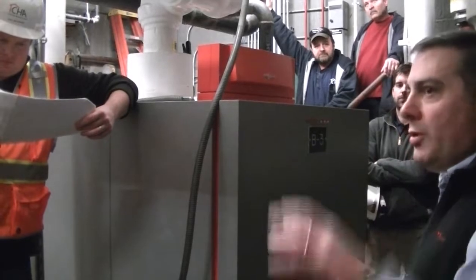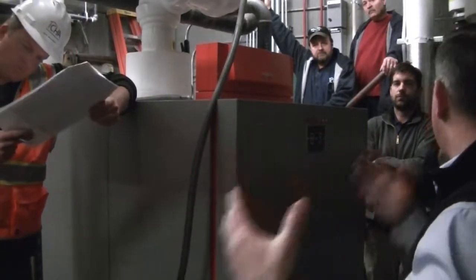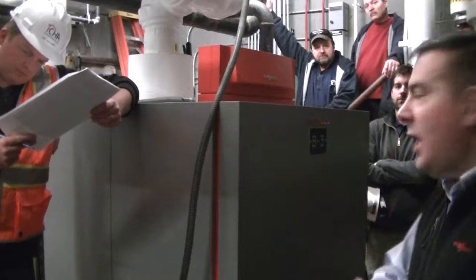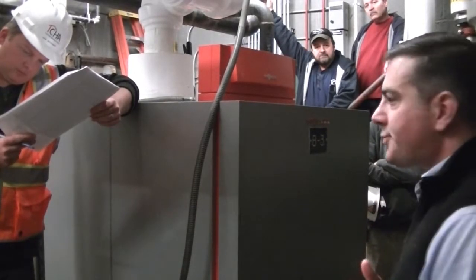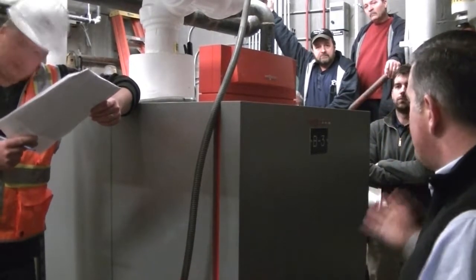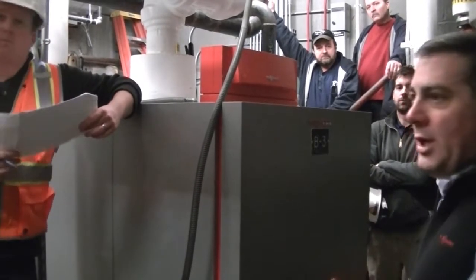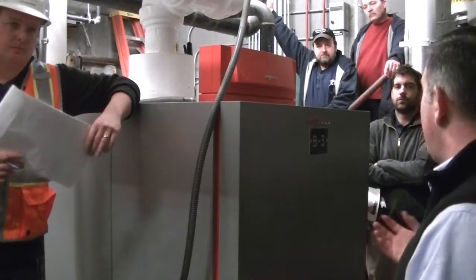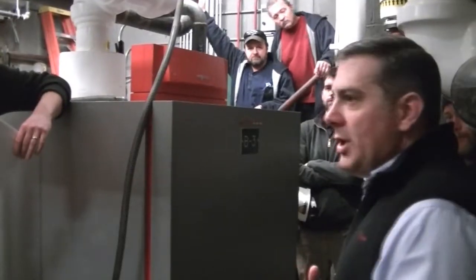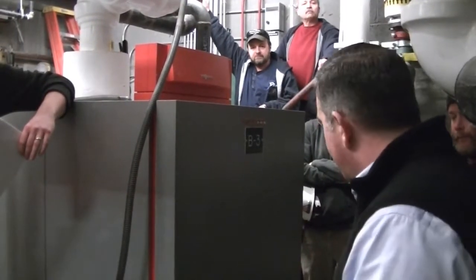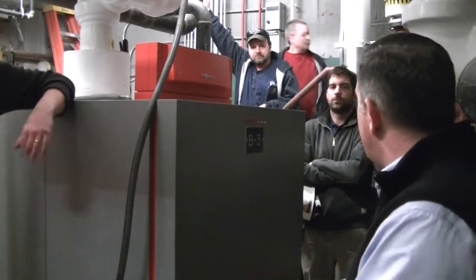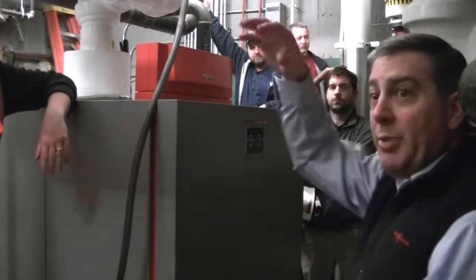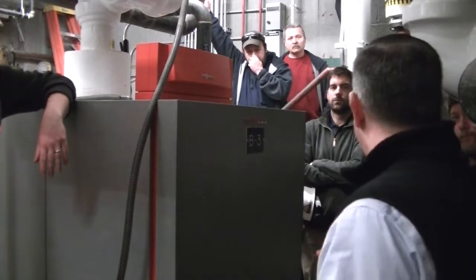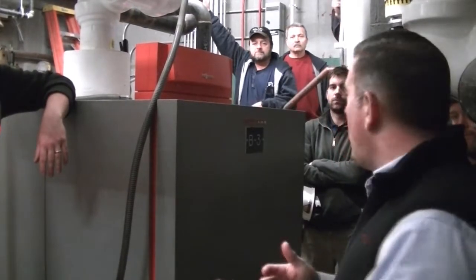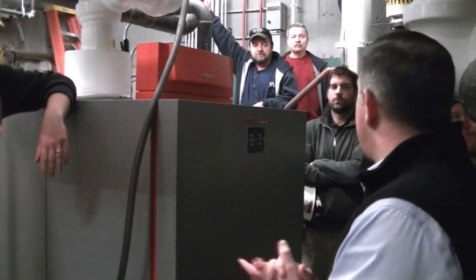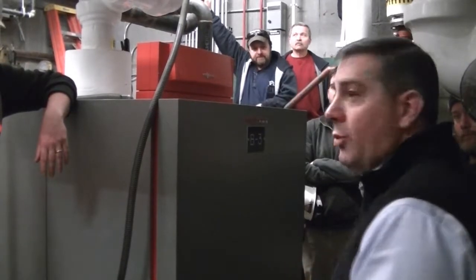So our lead boiler is down here. The lead boiler is the one that has the system control on it. So it's probably better to focus on this room than on the other room. The 4 boilers that we have here today are gas-fired condensing boilers. A condensing boiler is different than a conventional boiler that you may have had here in the past. With conventional boilers, you'd have a fire inside the firebox. The flame would heat up the casting, and the flue gases would go through that casting and up and out the chimney, with exit flue gas temperatures somewhere in the 300, 400, 500, 600, 700, 800 degree range, depending on how efficient or non-efficient the boilers were.